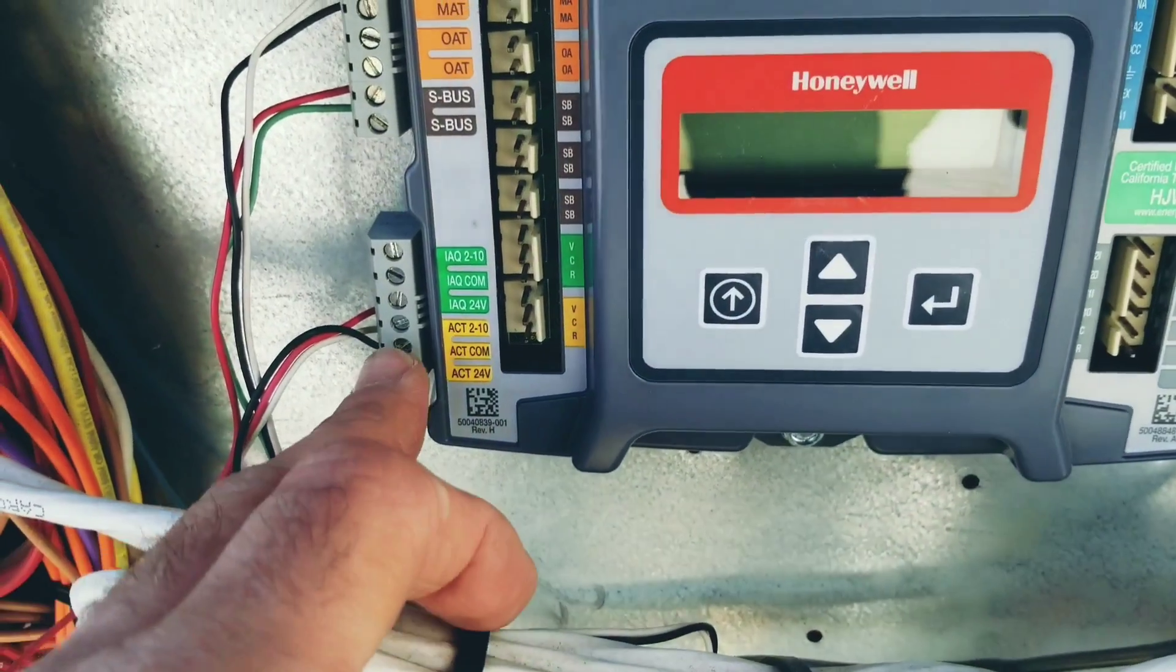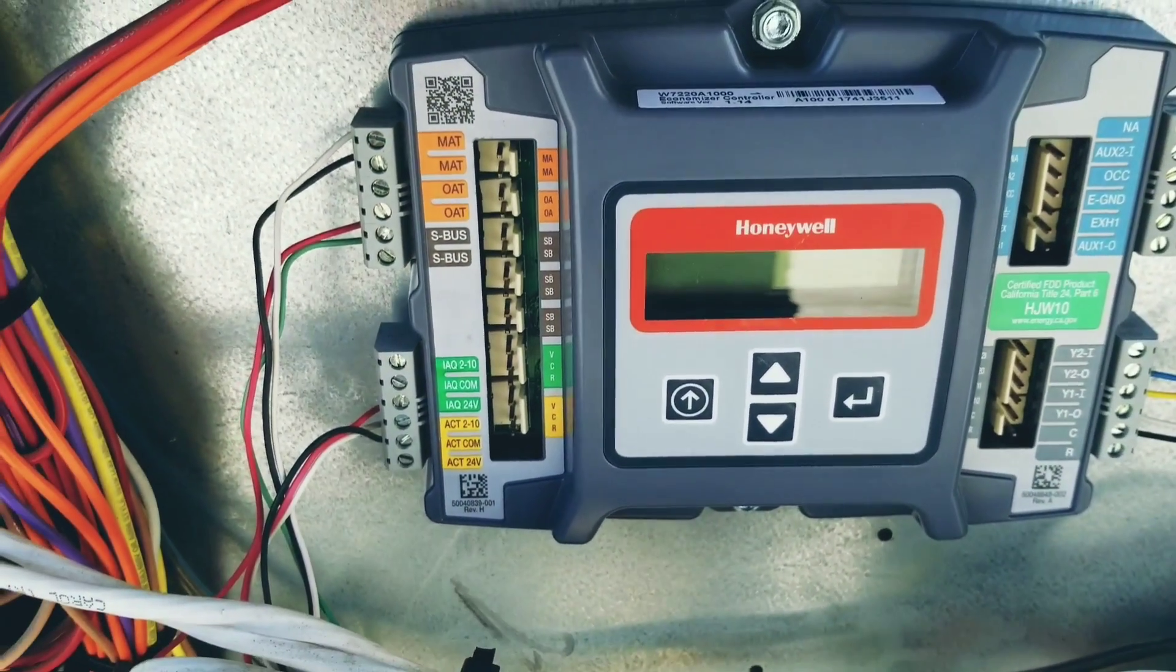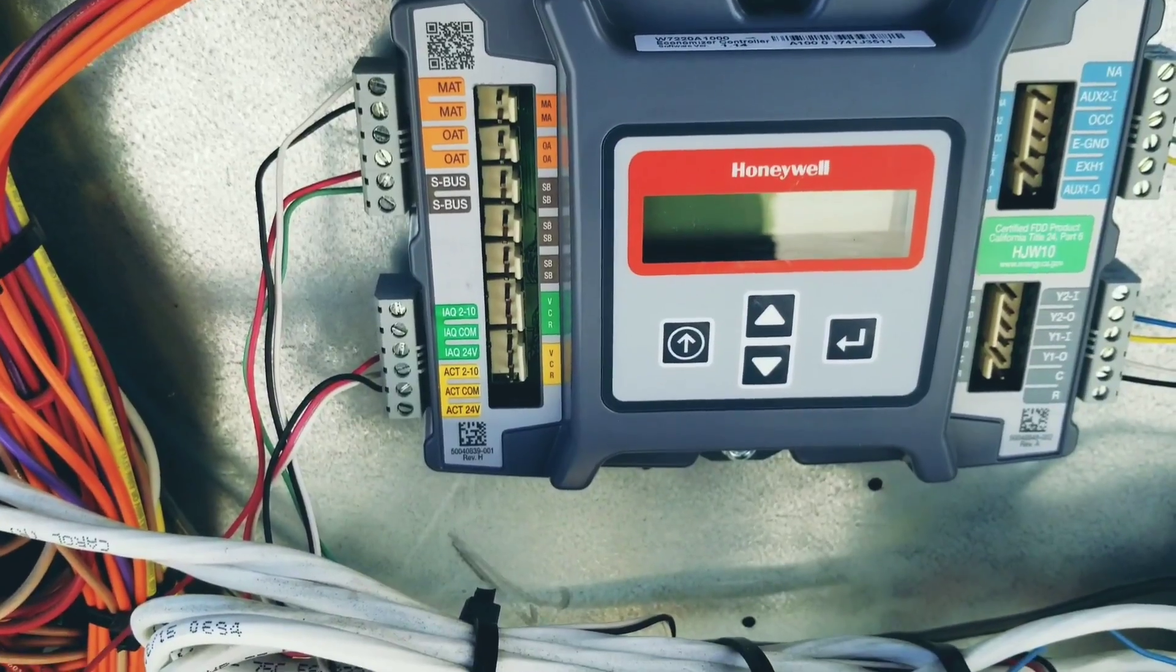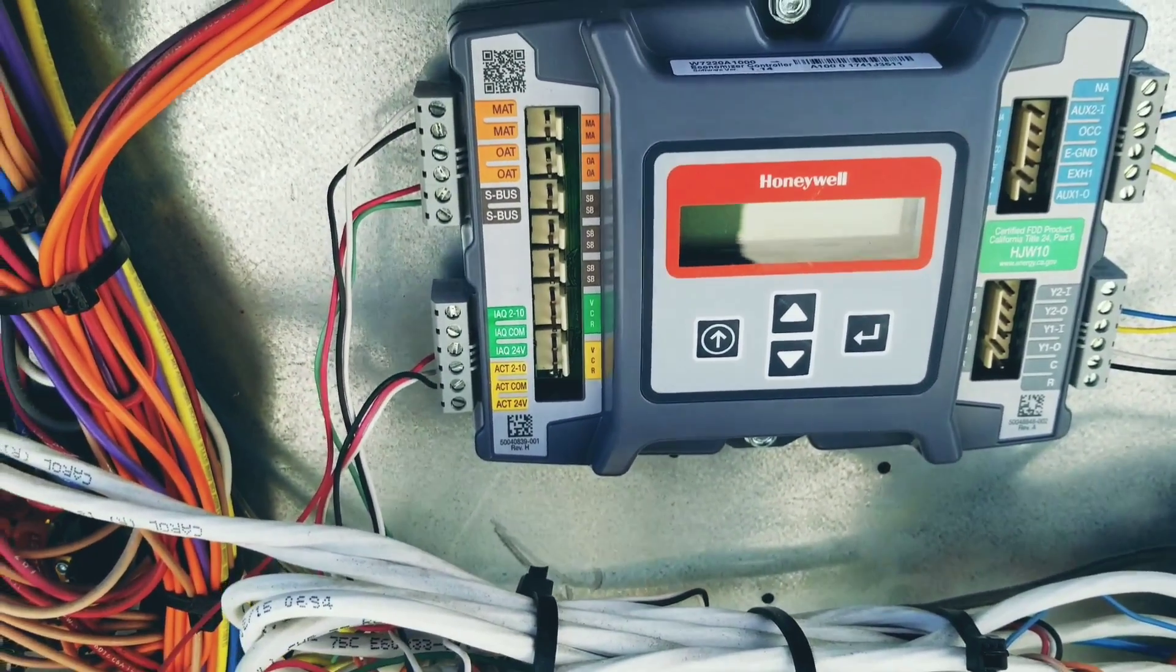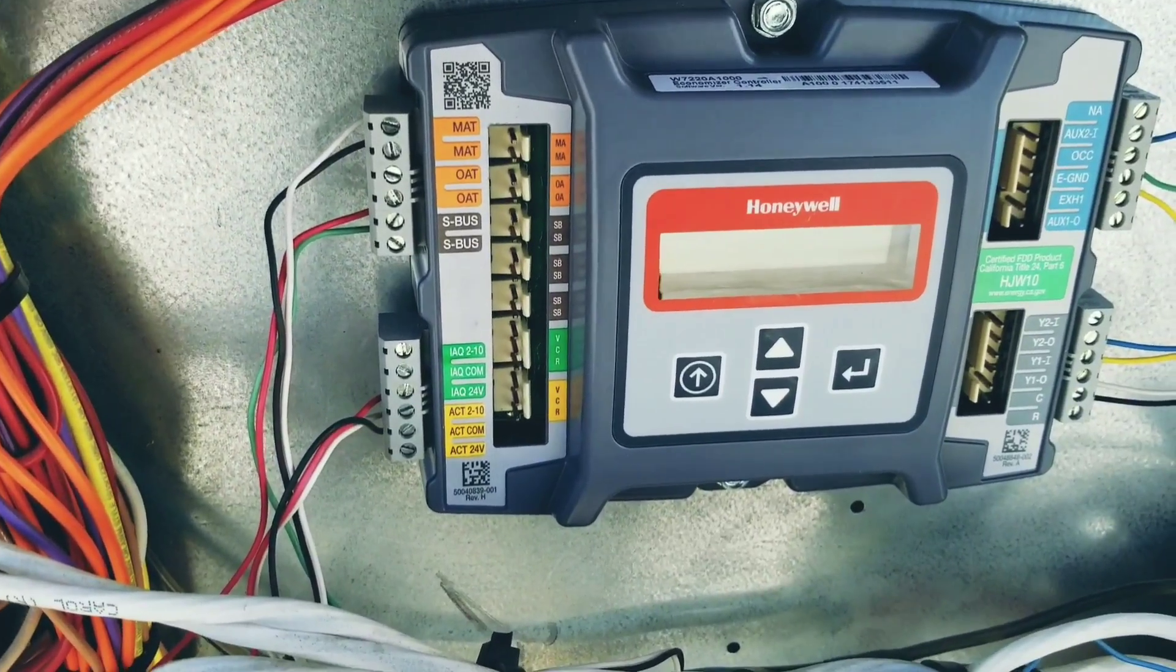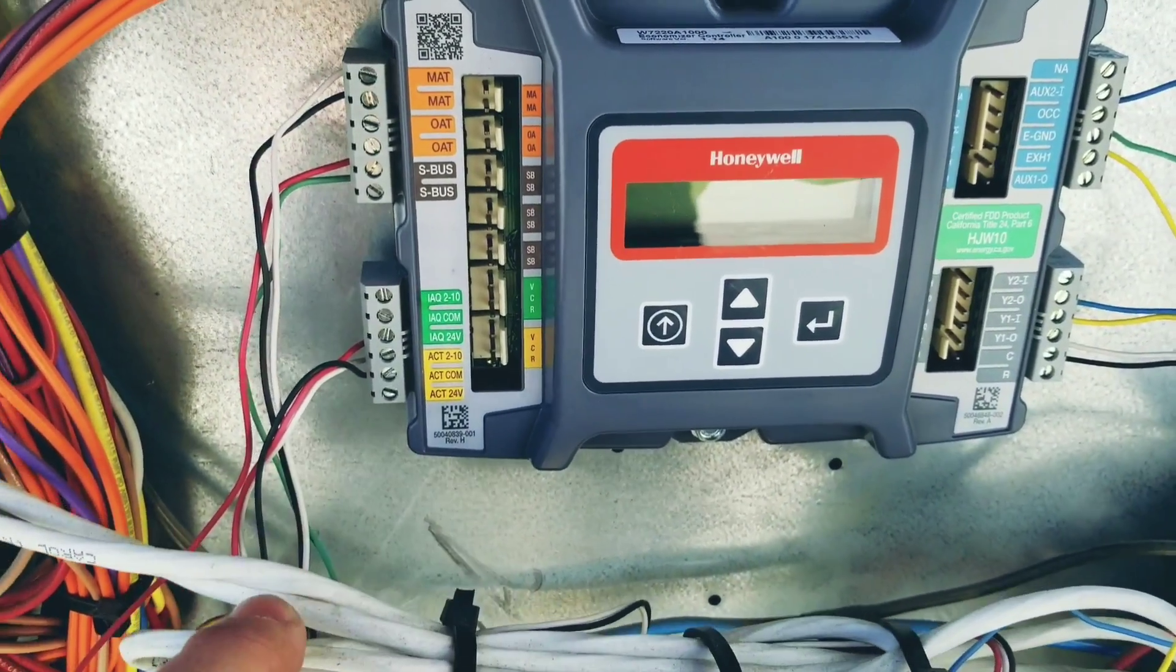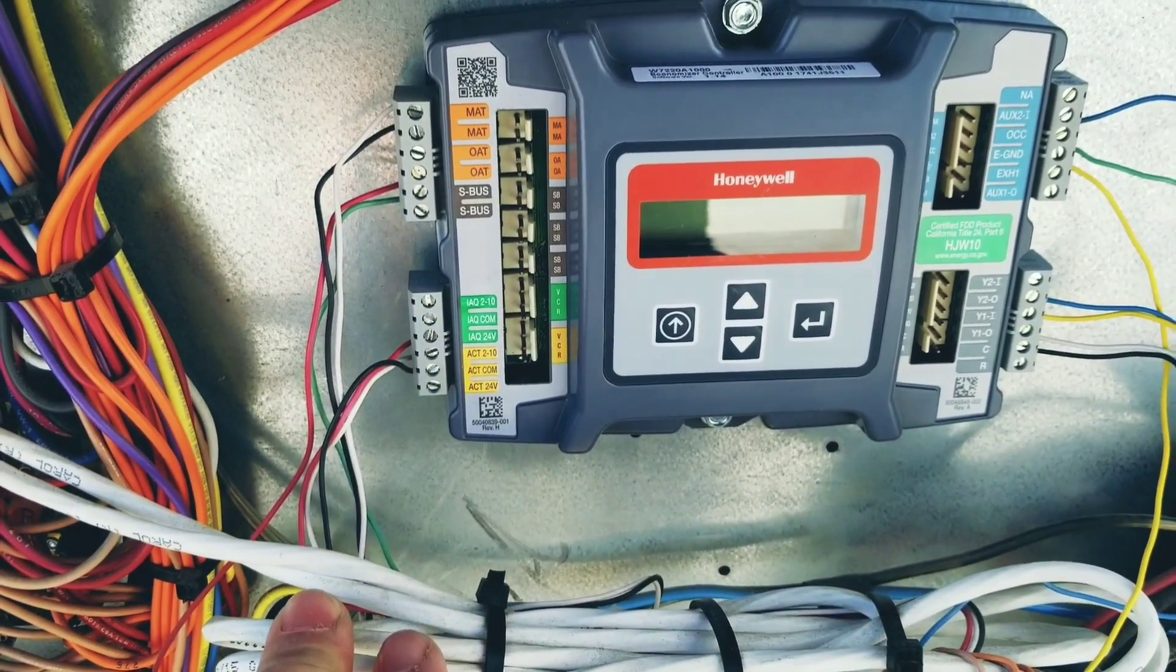I've plugged this back in—same issue. Fan starts and stops every few seconds or every 30 seconds or so. That's with the motor unplugged. So that tells me the motor is not causing this issue. That tells me something in the wiring is causing this issue.